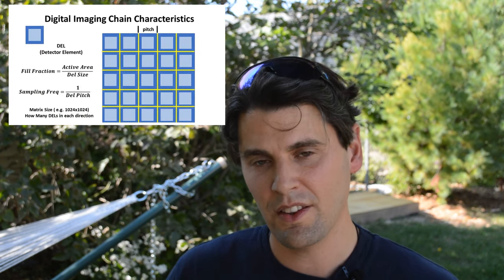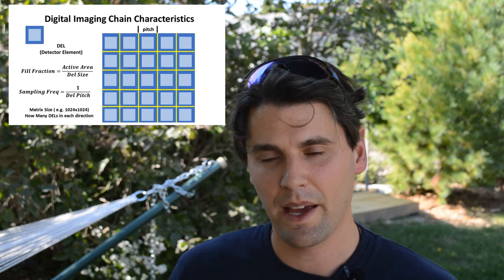In general, you can now appreciate that there are trade-offs when making these kinds of systems in terms of cost and the type of imaging you're going to do. You're going to want more samples and a larger dynamic range, but you're trading those two things off. If you have a smaller dynamic range to support, you potentially can have finer sampling over that same dynamic range. I'm Brian Nett — click on the next video about detector definitions on a flat panel matrix: what is a DEL, what is the active area, matrix size, sampling frequency, and other important things.